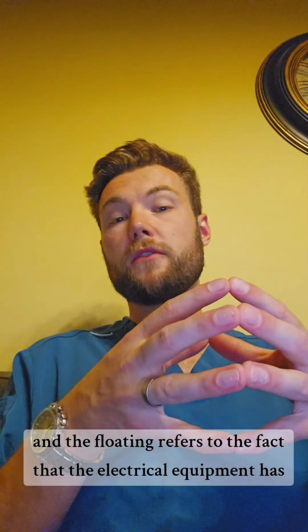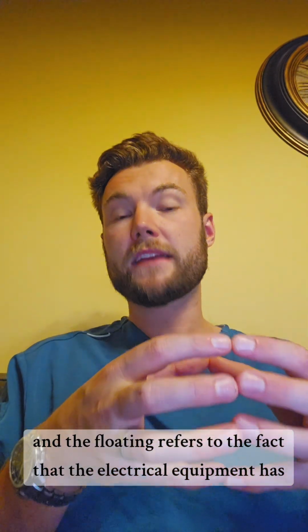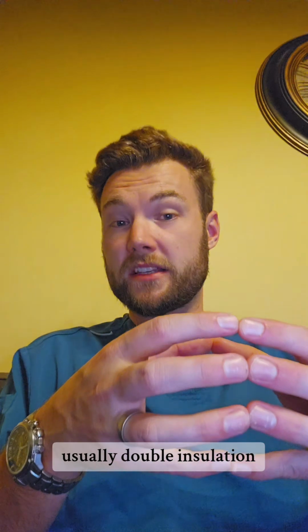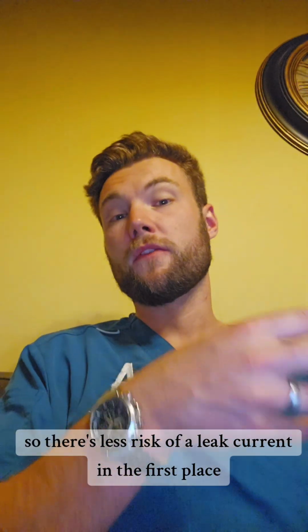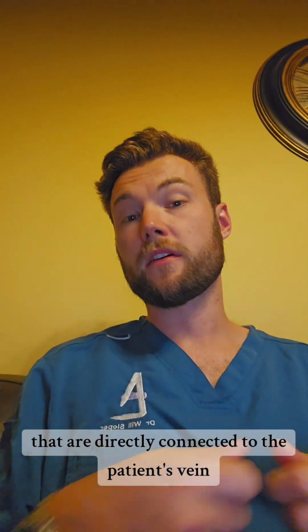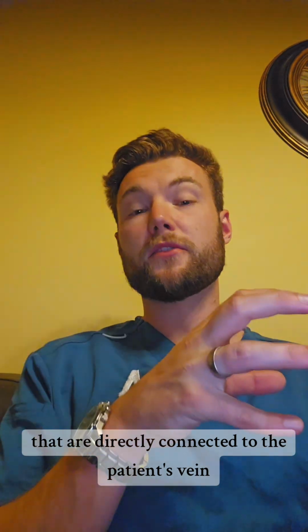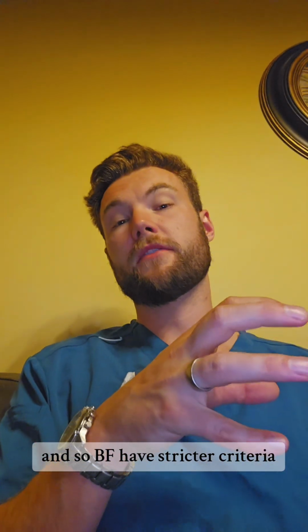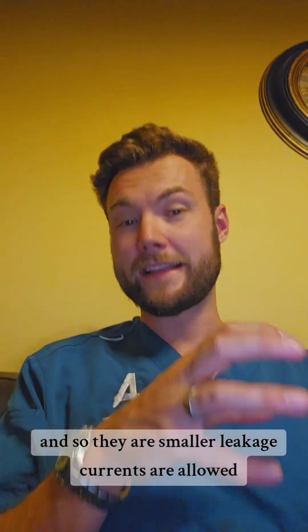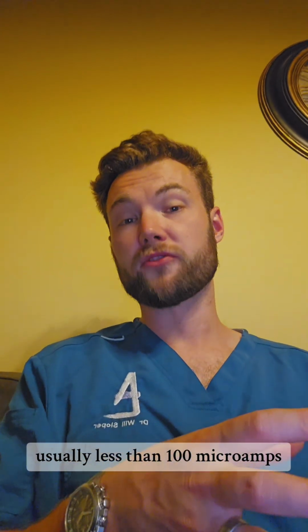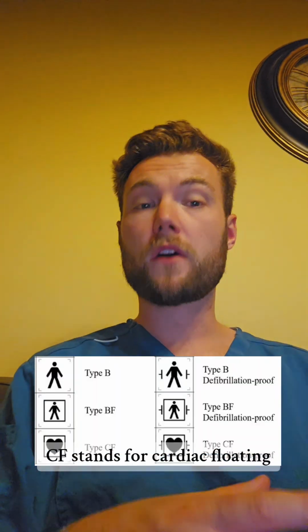BF stands for body floating, and the floating refers to the fact that the electrical equipment has usually double insulation, so there's less risk of a leak current in the first place. And these are things like your infusion pumps that are directly connected to the patient's vein. And so BF have a stricter criteria, and so smaller leakage currents are allowed, usually less than 100 microamps. And CF stands for cardiac floating.